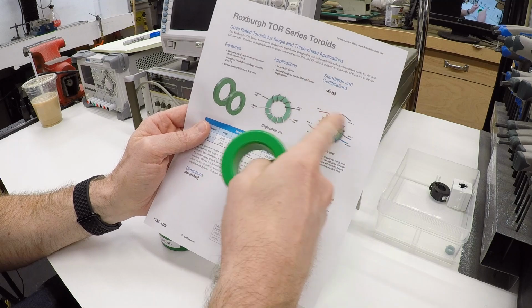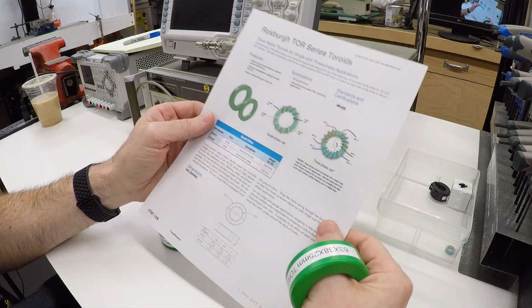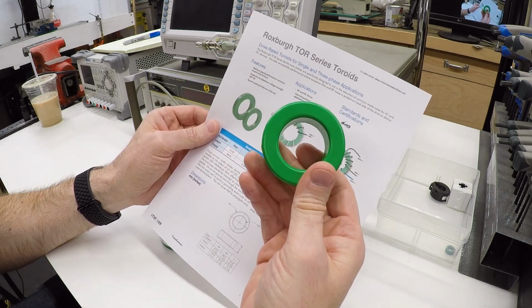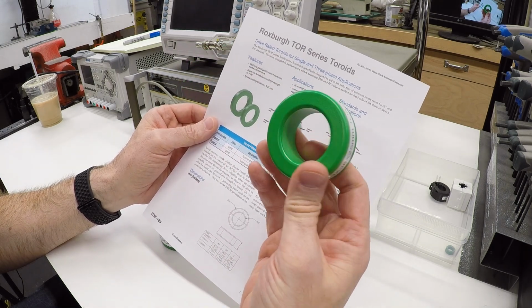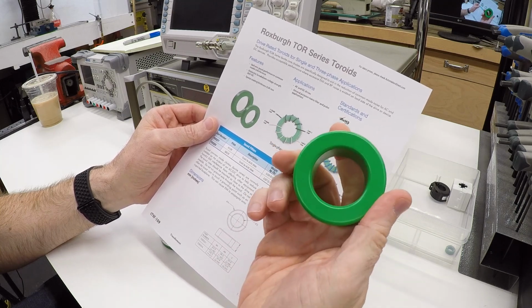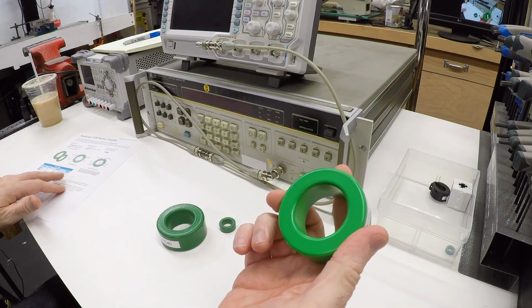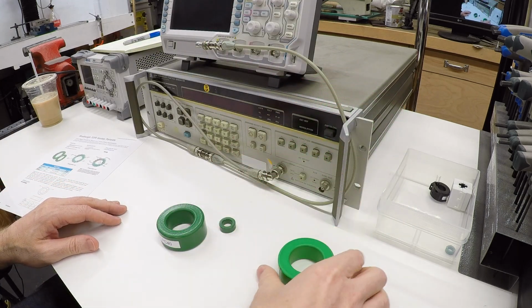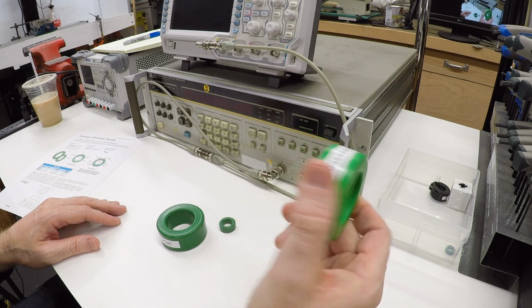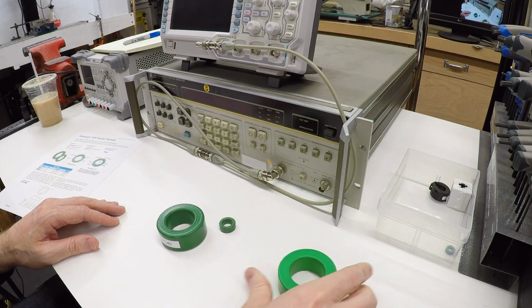Great, I can install it. They show you how to wire it. And aside from the physical dimensions, they really don't give you anything else. They don't tell you anything about magnetic permeability or core saturation. They don't even tell you what the material is that the core is made of. There are dozens of core materials designed for different applications. So this is one way you find them, saying, buy this, this is for a drive. And again, these can be from industrial suppliers for a ton of money, or discount ones for $12, $13.